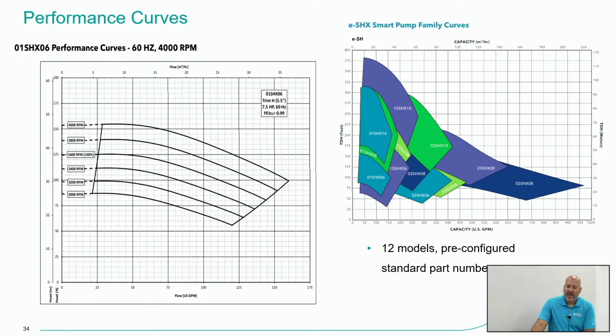So if you're looking at our performance curves, they could look a little bit different. We show you multi-speed curves all the way from 3,000 RPM to 4,000 RPM, but we still kind of labeled that 3,600 RPM as 100%, as that's what customers are traditionally used to seeing as the full speed of a product. But like I said, we can essentially overspeed the ESH up to 4,000 RPM due to the motor's capabilities. So we're showing you those curves as well.